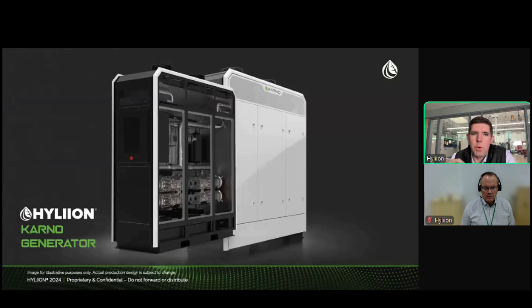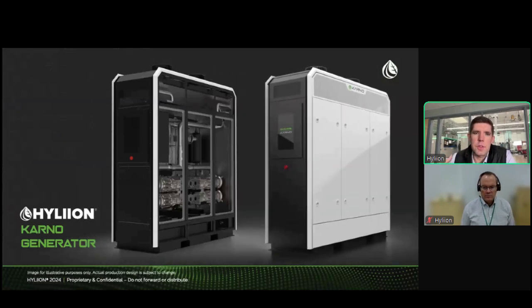So we then take that 4-shaft array, and we put it into an enclosure. You can see on the slide that box is comprised of everything from fans and radiators and pumps in order to run the system. That product will produce 200 kilowatts of electricity. This is really an equation of you bring fuel in - you can use various fuels, pipeline natural gas, on-site storage of diesel or propane. The generator really doesn't care what fuel you're providing it, and it then takes that fuel and converts it to electricity at the benefits I mentioned previously.